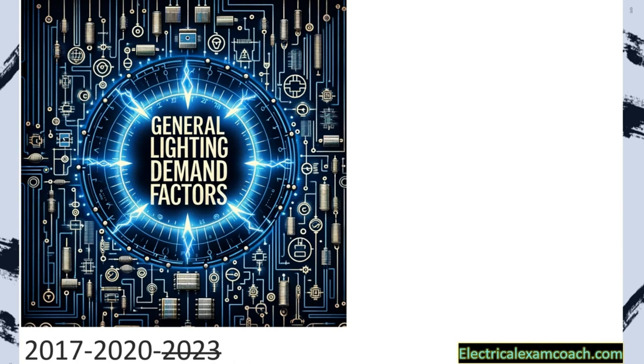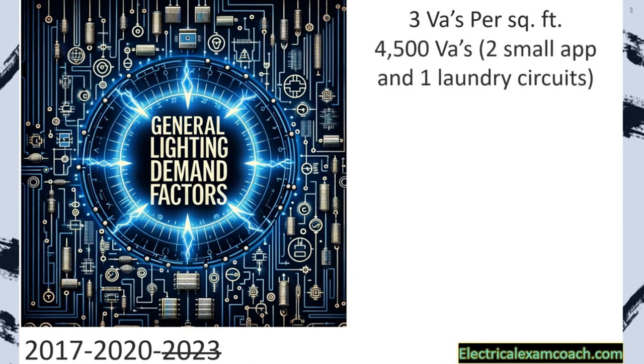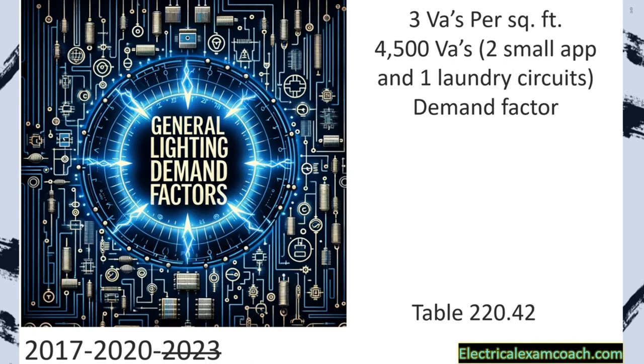Welcome back. I am the Electrical Code Coach from ElectricalExamCoach.com, and this is Lesson 4.2. Now we're going to learn how to apply the demand factor to the general lighting load. At the beginning of the program, we learned it was 3 VAs per square foot with 4,500 VAs added for two small appliance and one laundry circuit. I didn't teach you the demand factor for this earlier because it's complicated without knowing what a demand factor is — but now you're very familiar, so let's head to Table 220.42.